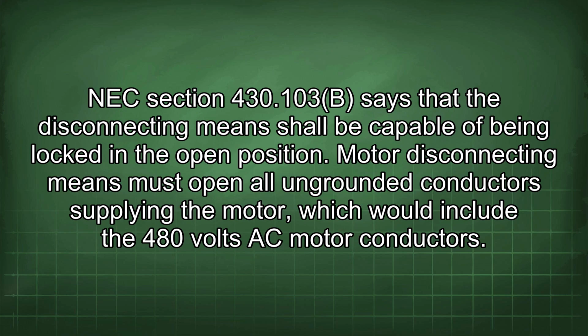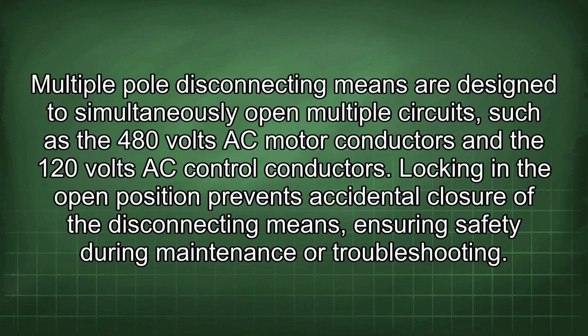NEC section 430.103(B) says that the disconnecting means shall be capable of being locked in the open position. Motor disconnecting means must open all ungrounded conductors supplying the motor, which would include the 480 volts AC motor conductors. Multiple pole disconnecting means are designed to simultaneously open multiple circuits, such as the 480 volts AC motor conductors and the 120 volts AC control conductors.